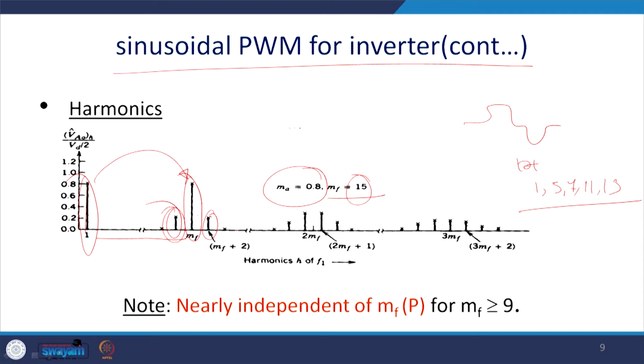Similarly, at 2 MF you also get 2 harmonics. So, here also at 1550 and 1450 you will get another 2 spectrum, and the same way so on. Ultimately, it shifts the spectrum to the higher frequency region. Since your power system itself is a low pass filter, this high frequency component can be eliminated by a very small size filter, and thus your drives become compact.